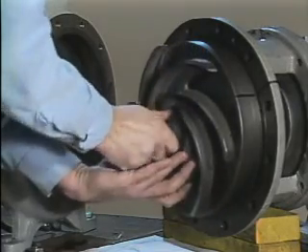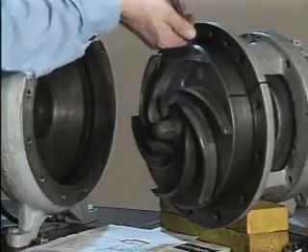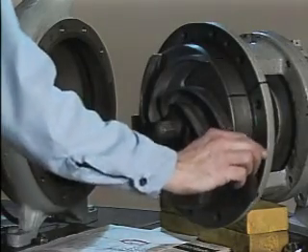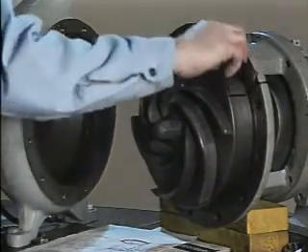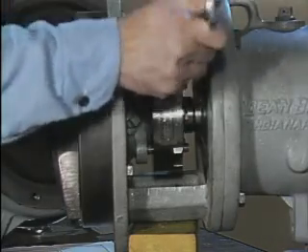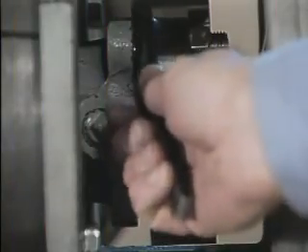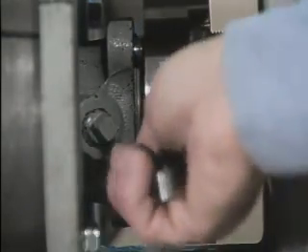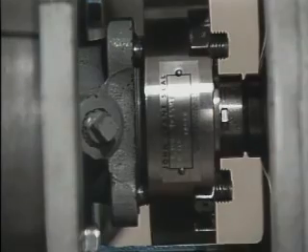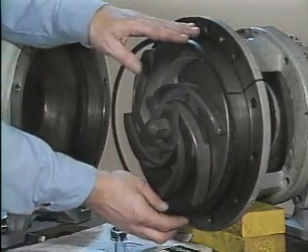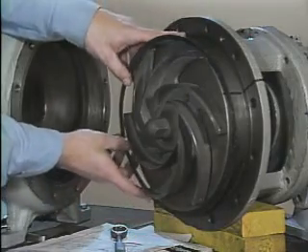Then the impeller is installed, and the clearance between the impeller and the back plate is checked to make sure that the components are properly positioned. Then the gland plate is bolted to the stuffing box. Next, the gap between the stuffing box and the gland plate is measured to ensure that the gland plate bolts have been tightened properly.